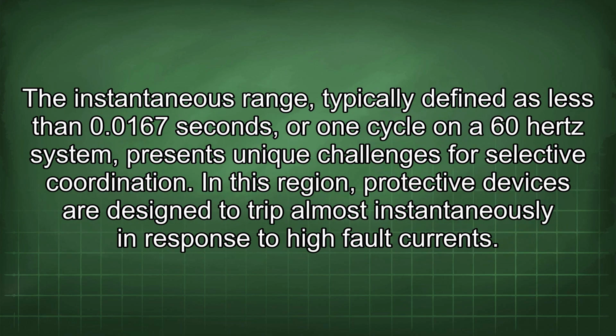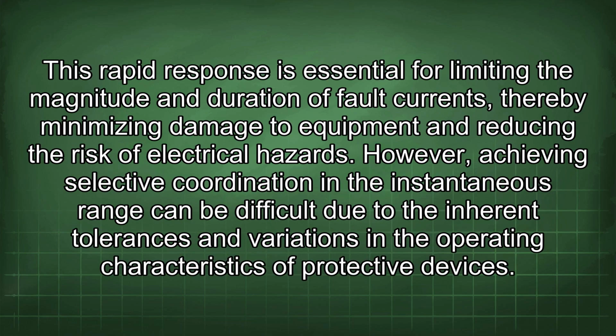The instantaneous range, typically defined as less than 0.0167 seconds, or 1 cycle on a 60 Hz system, presents unique challenges for selective coordination. In this region, protective devices are designed to trip almost instantaneously in response to high fault currents. This rapid response is essential for limiting the magnitude and duration of fault currents, thereby minimizing damage to equipment and reducing the risk of electrical hazards.